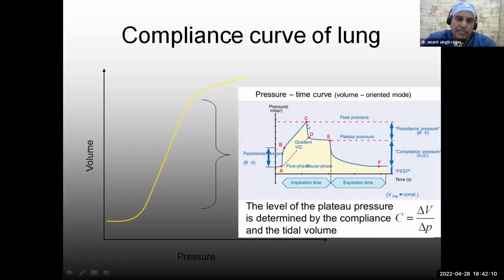Now, after that, what has happened? There is a pause in the ventilation. Inspiration is also stopped, expiration is also stopped, and everything is paused. So there is a drop in the pressure, but since expiration is also not taking place, the air gets redistributed inside the lung during the pause time from D to E, and then from E the expiration starts. So you can see here, this is the inspiratory phase, this is the expiratory phase.